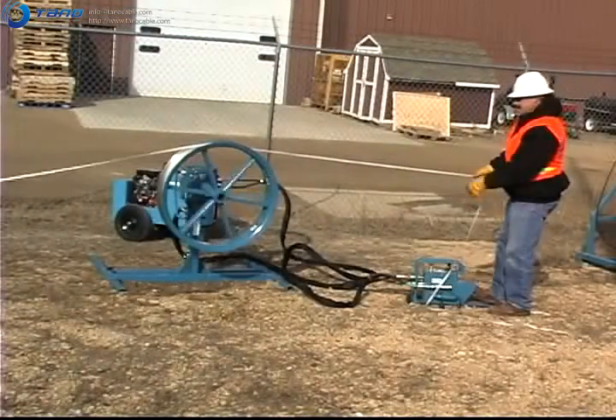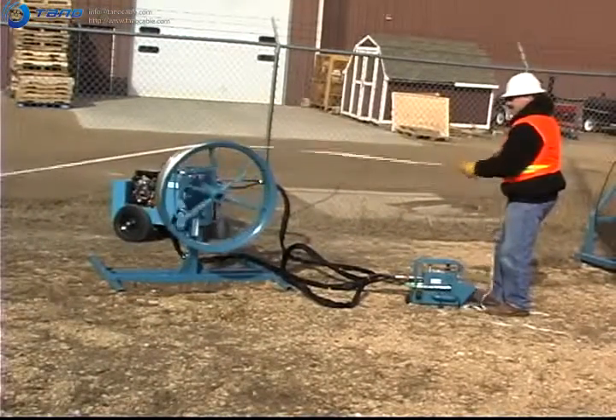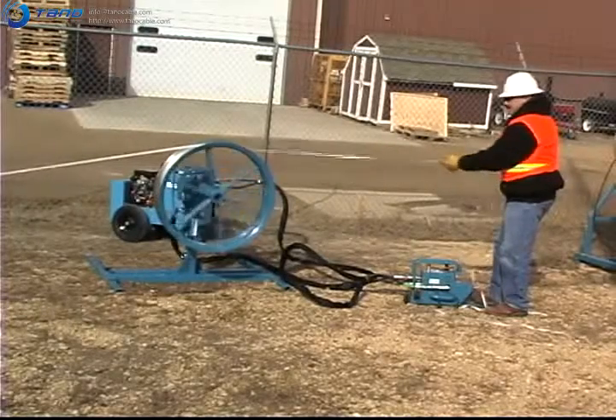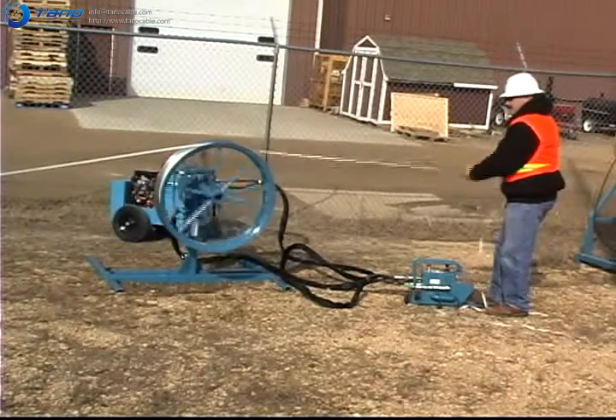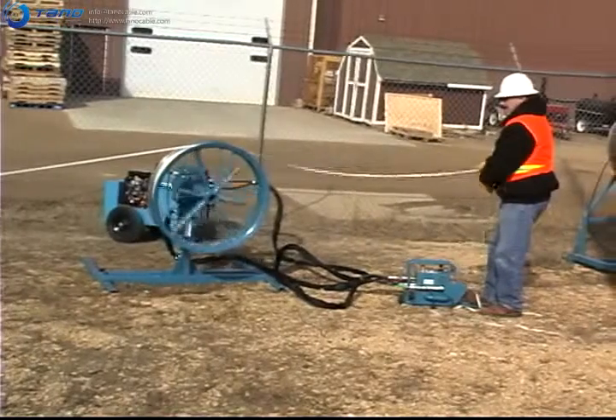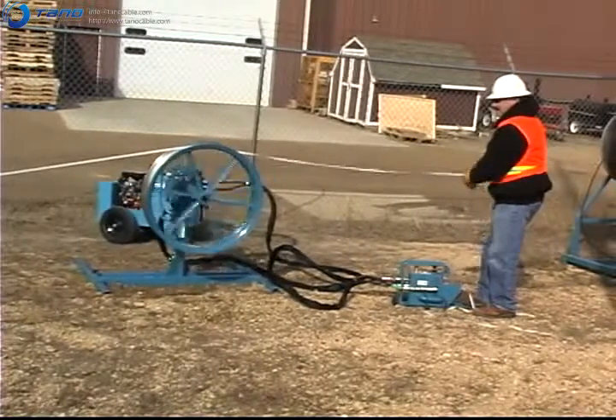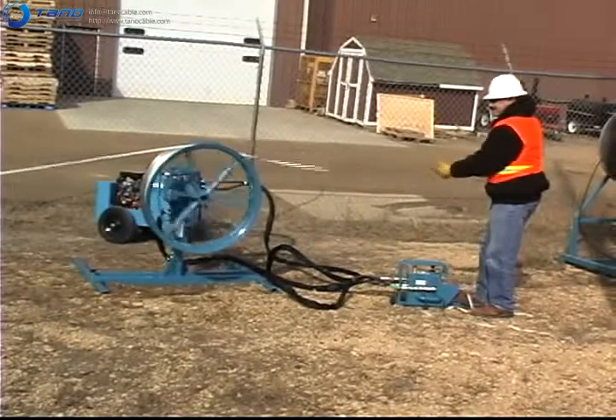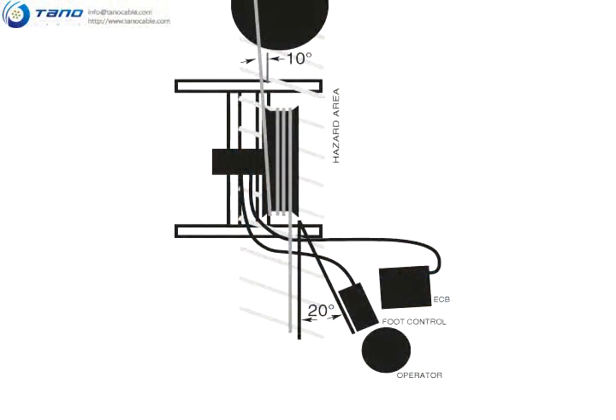Resume pulling. Remove any slack or excess pull line before increasing the puller's speed. Attend the line coming off the capstan to avoid any tangles and keep some tension on the line so that the capstan grips the pull line. Never wrap the line around your hand, arm, foot, or leg, and always be prepared to release the line. Stand at least 3 to 4 feet away and at a 20-degree angle from the capstan. Wear gloves to avoid rope burns and abrasions.